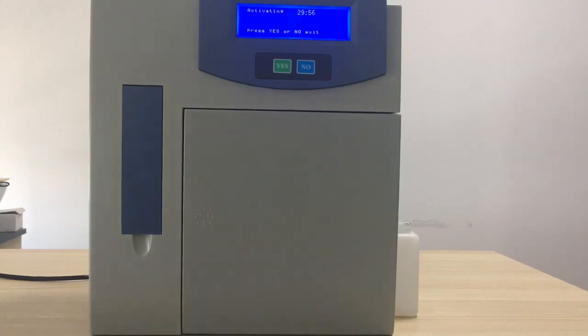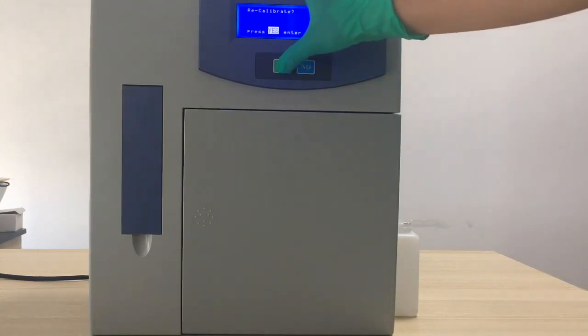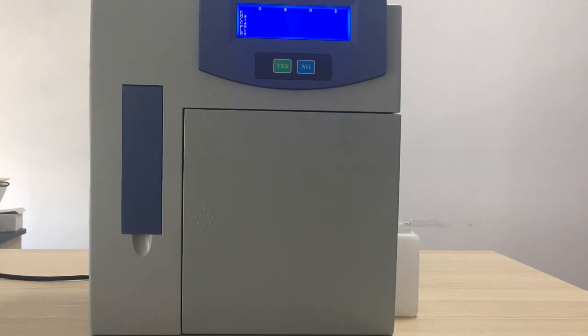After auto checking finishes, it will ask you to do activating. For our new brand, you don't need to do activating, but you need to do the calibration. Calibration is the basis for each measurement, so you have to complete the calibration successfully before running the tests. When calibration finishes successfully, it will give a measurement for calibration solution A. After this, it will go into the main menu. Then we can do the real sample test.